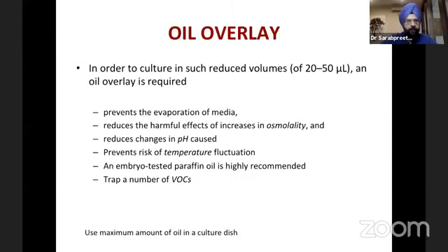Coming to oil, an oil overlay is recommended, especially when you are culturing microdroplets, and it prevents the evaporation of media, thereby decreasing the harmful effects of increase in osmolality, changes in pH, and preventing risk of temperature fluctuation. So an embryo-tested paraffin oil is recommended, which also helps in trapping a number of volatile organic compounds.